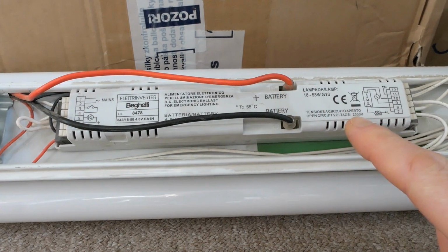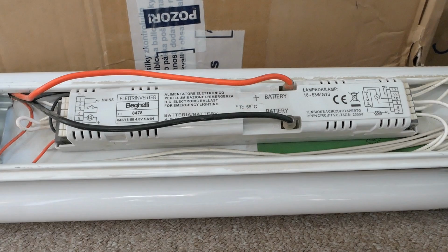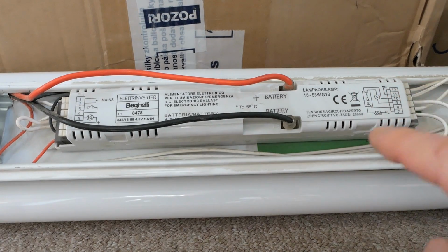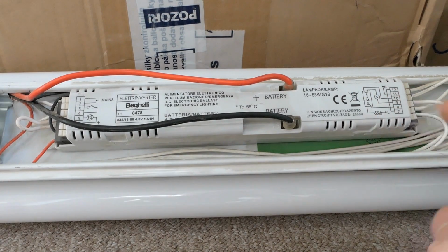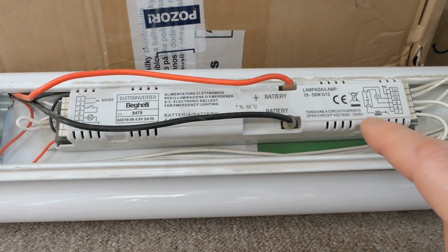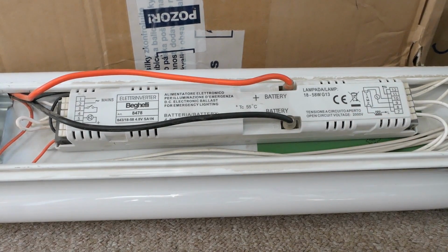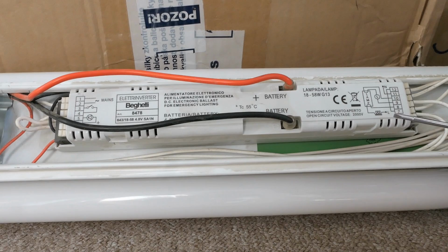Open circuit voltage 2000 volts, bloody hell. And it's showing a lamp with a starter and a magnetic ballast. It's weird. This one was meant for a magnetic ballast fixture, but they botched it on an electronic one. Here's the live going via the inductor to the lamp, and then the connection to the starter actually goes through this one, so it's probably disconnecting the starter when it's running on a battery, and it's also disconnecting the neutral from one of the pins when it's running on a battery.